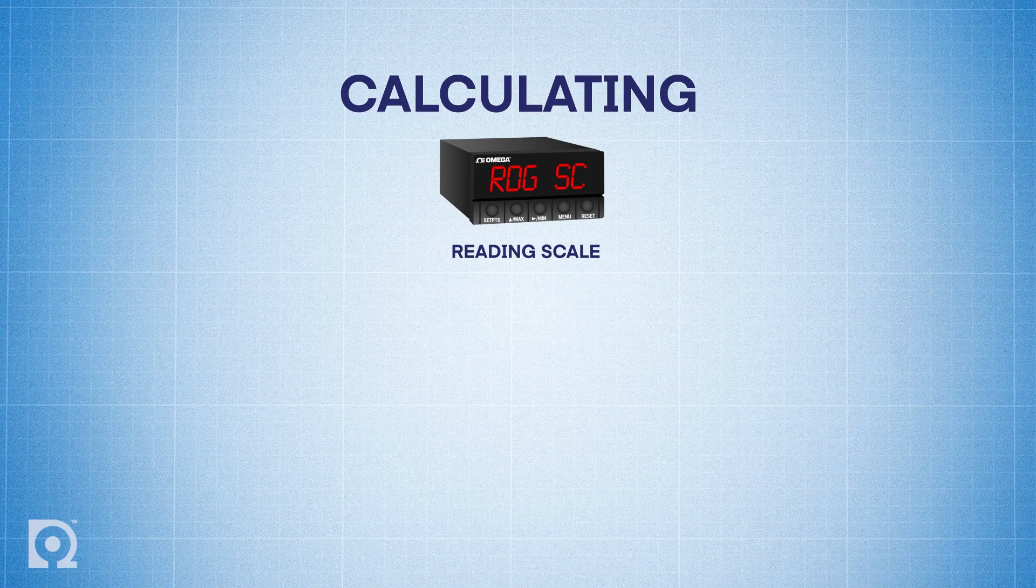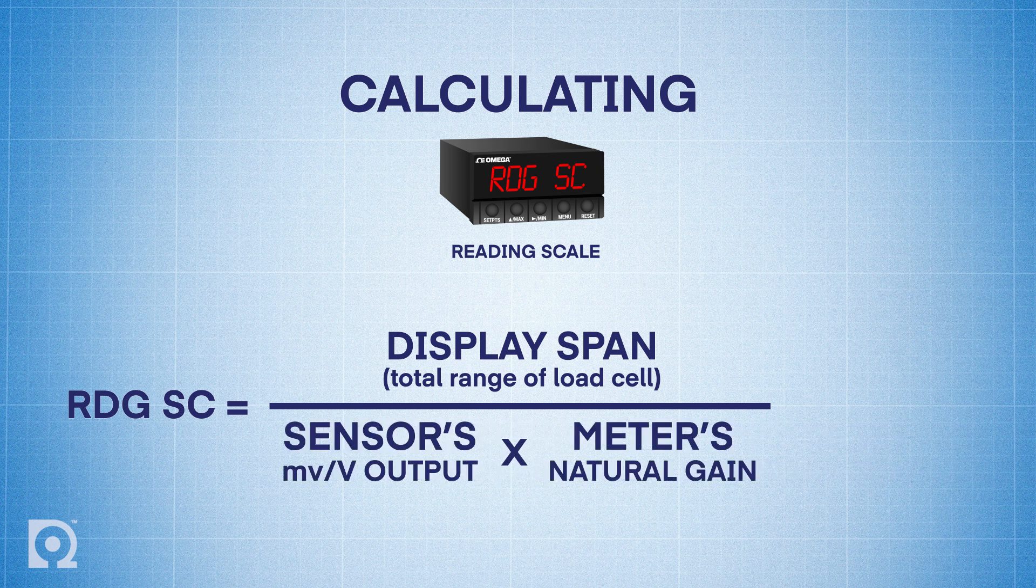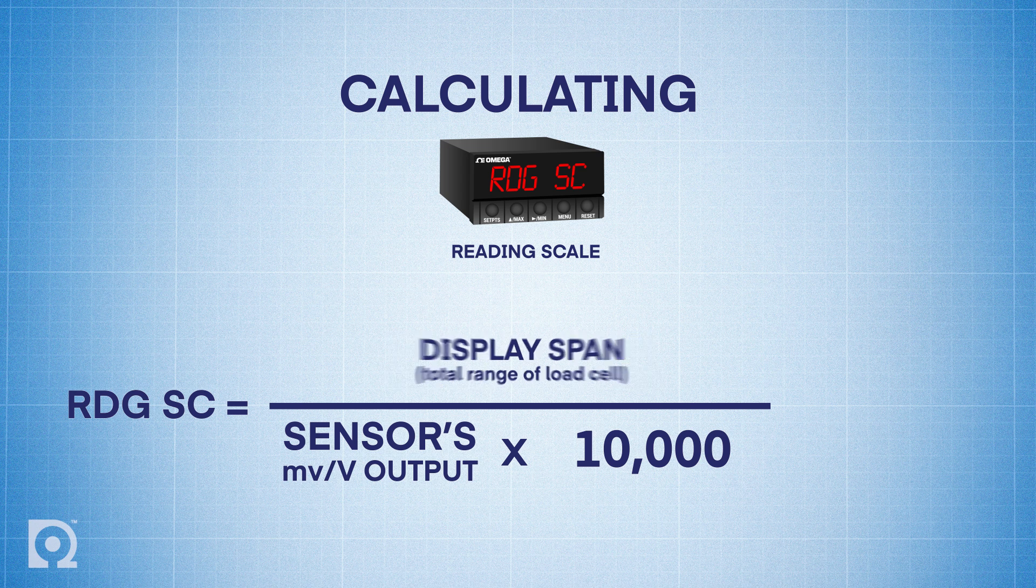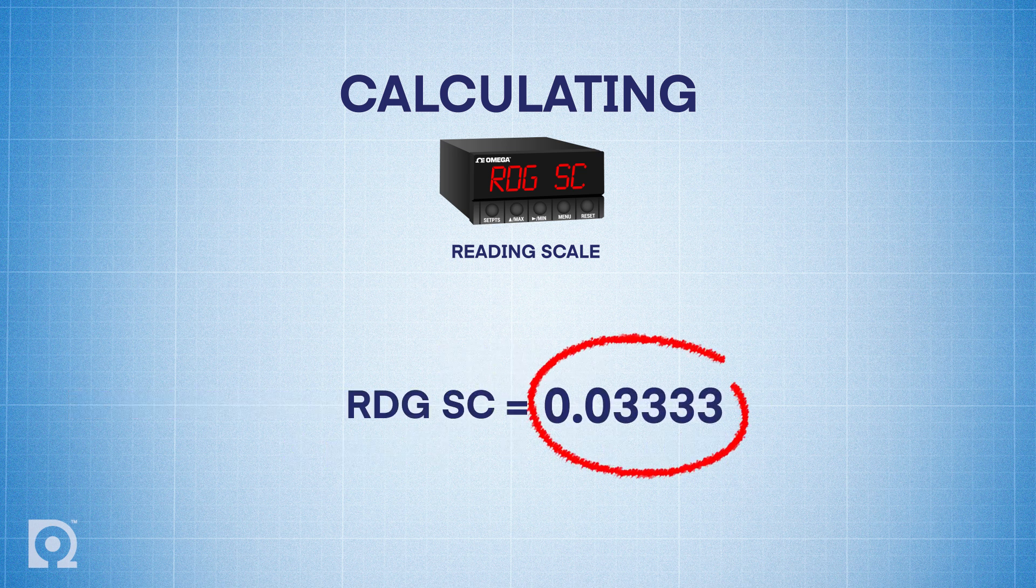To calculate your RDG-SC, we'll use the following formula. RDG-SC equals the display span, in other words, that's the total range of your load cell, divided by the sensor's millivolt per volt times natural gain of the meter, which also happens to be 10,000. So for example, in this instance, we have a thousand pound load cell, and it has a three millivolt per volt sensitivity. This sensitivity can be found by referring to your calibration certificate that shipped with your load cell. So your RDG-SC would be thousand divided by three times 10,000, which comes up to 0.03333.